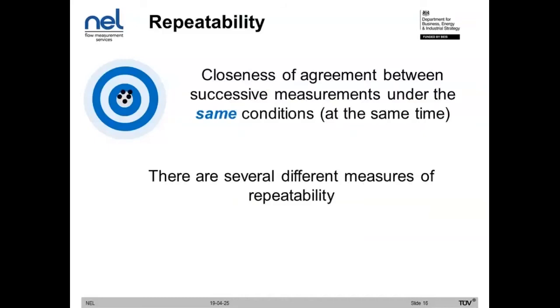Repeatability. This refers to the closeness of agreement between successive measurements of the same measured parameter under the same conditions at approximately the same time. The example that easily illustrates this is if you have a balance and you use it to measure the weight of an object repeatedly, you'll find that you get a spread of results, and hopefully they're in very close agreement. Another example might be taking resistance measurements of the same resistor. Or additionally, you can take repeatability measurements of a flow meter as well, so you can establish the same flow conditions repeatedly and see how consistently the device performs.